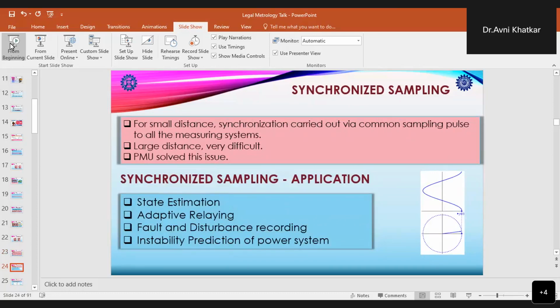Now, when we talk about this synchronized sampling, for small distances, this synchronization could be carried out by using a common sampling pulse for all the measuring systems. However, it is very difficult when we see a larger distance or when our complete grid is connected. So to solve this problem, PMU comes into picture. And by having this synchronized sampling, we have many types of applications which can be solved, for example, state estimation, adaptive relaying, fault and disturbance recording, and instability prediction of the power system.